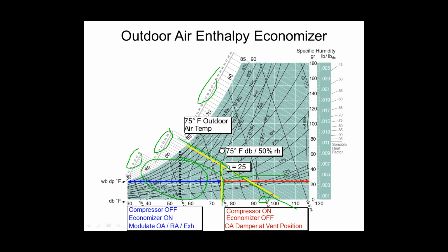And everything over here with the red arrow on it, that's going to be my compressor day. So I'm getting a little bit more in this shaded area that I'm making here. I love this pen thing. I know you guys probably hate it when I do it, but I love it. That shaded pen area there is more economizer days that I didn't have before. This shaded triangle over here is days I'm not going to run the economizer because it's too humid, and I shouldn't have been doing it to begin with. I just never had a sensor until now.